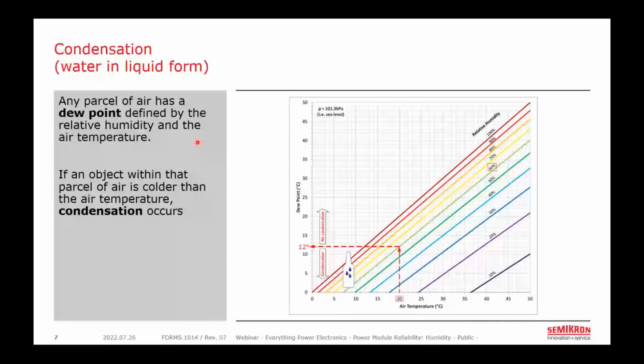And what's happening here is that in this room, we have a given humidity and temperature. For example, 60% relative humidity and 20 degrees Celsius air temperature. And so this graph here shows us the dew point for that given condition. So if we look at the intersection of that 20 degrees Celsius room temperature and the 60% relative humidity line, we can see that the dew point over here is 12 degrees Celsius.